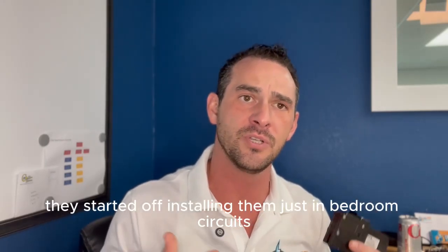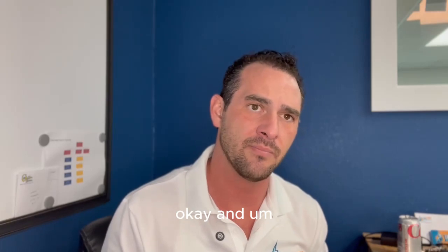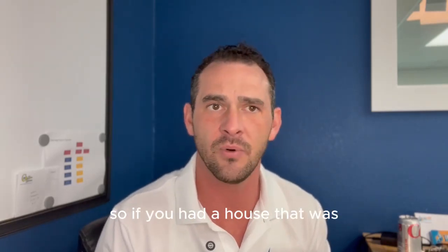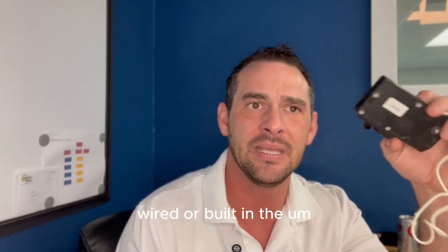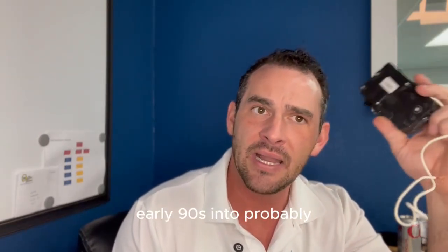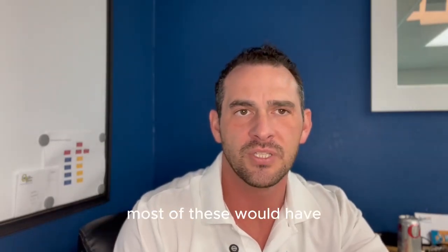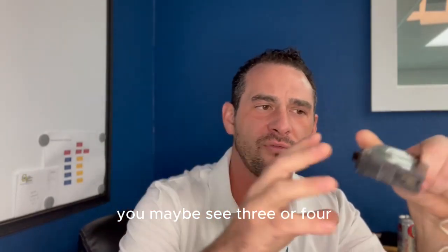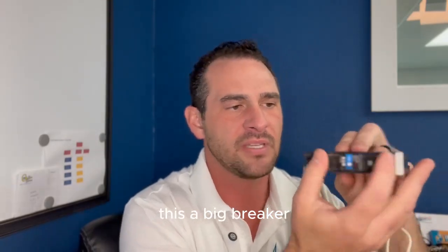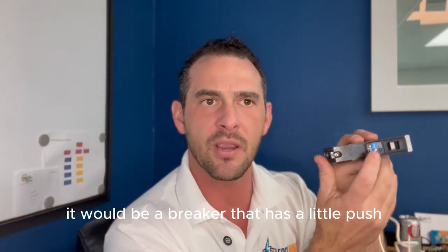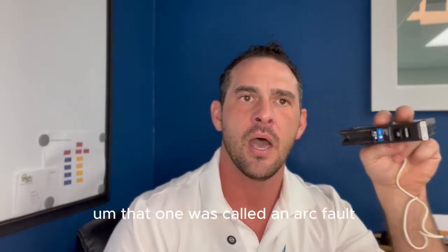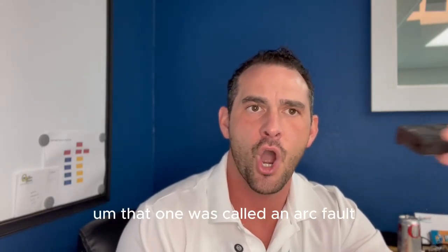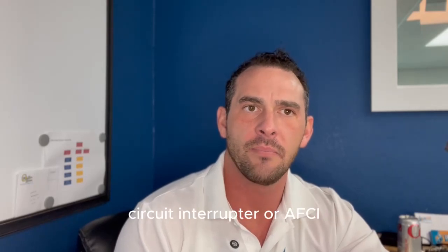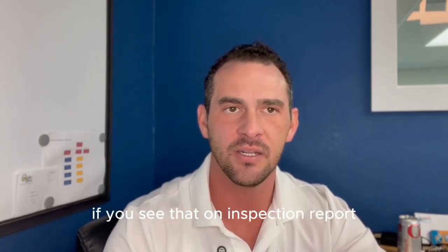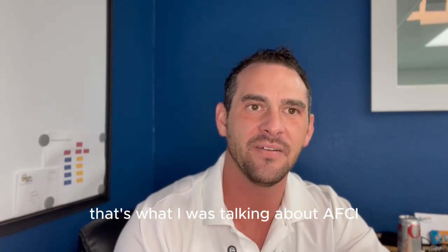They started off installing them just in bedroom circuits, okay? And that was the code. So if you had a house that was wired or built in the early 90s into probably 2005-ish or so, most cities, you'd maybe see three or four of these types of breakers. This is a big breaker, but on the cover, it would be a breaker that has a little push button on it. That one was called an arc fault circuit interrupter, or AFCI. If you see that on an inspection report, that's what it's talking about, AFCI.